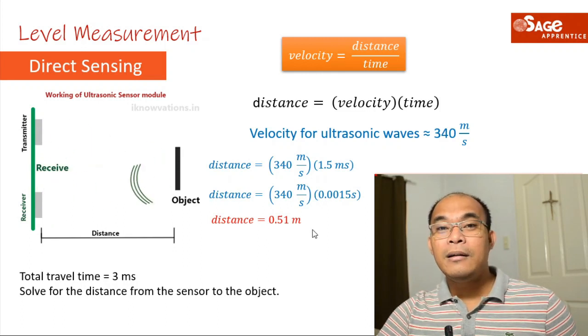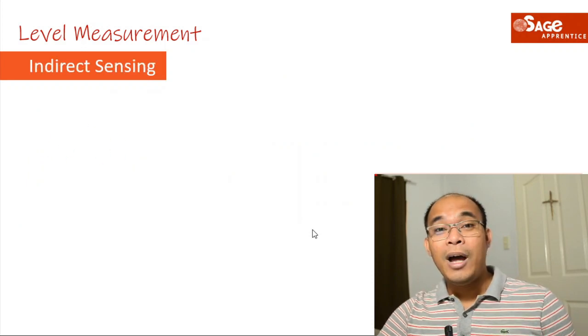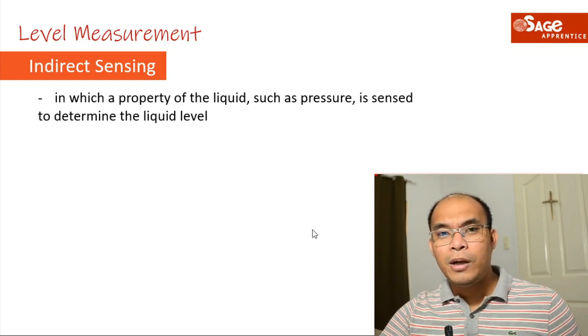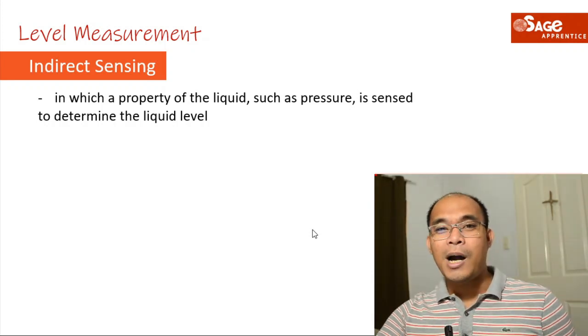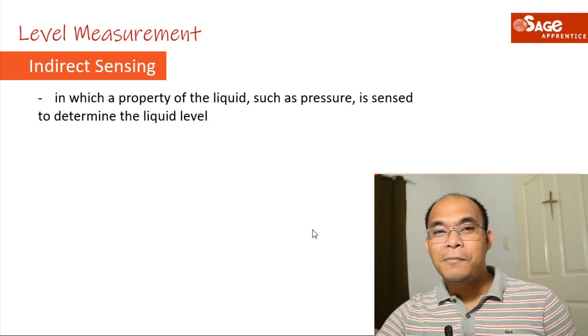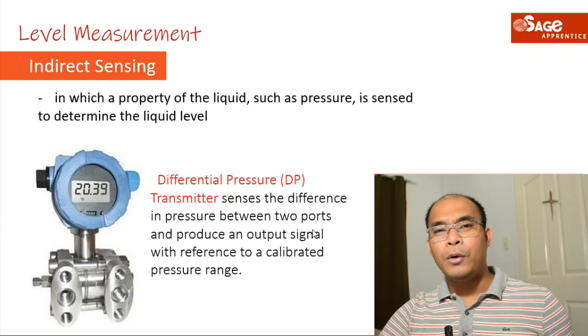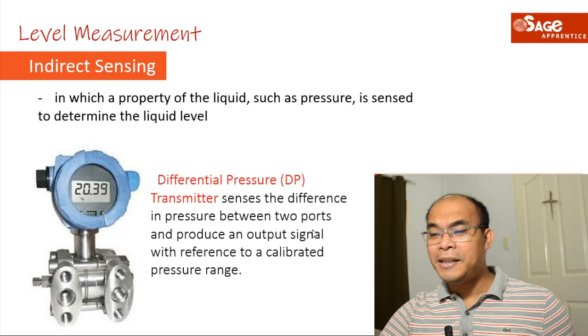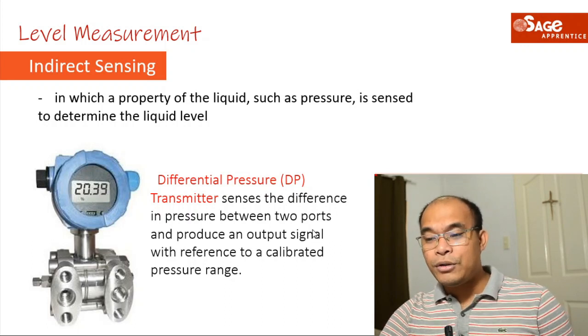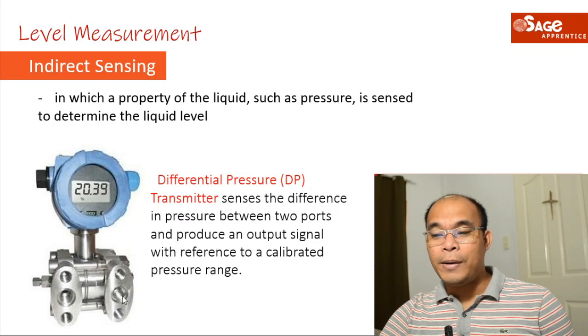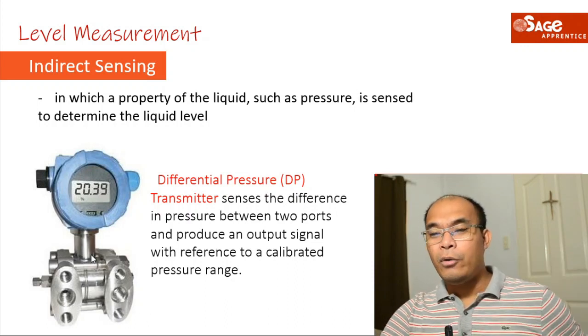Now we look at indirect sensing, where a property of the liquid — such as pressure — is sensed to determine the liquid level. The physical quantity itself is not directly measured; instead, related quantities such as pressure are used. The most common device used here is the differential pressure (DP) transmitter, also called the delta-P transmitter. This transmitter senses the difference in pressure between its two ports and produces a signal referenced to a calibrated pressure range.